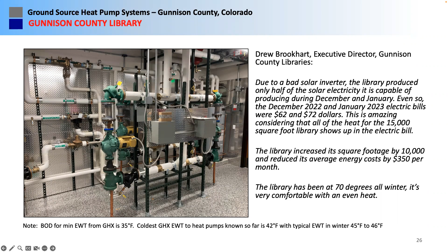The entire design team and contractors, everyone pulled together, with great communications during design and construction. And the system is working a lot better than we projected. If you'll notice on the bottom of the slide, the basis of design for the ground was a minimum of 35 degrees to the heat pumps, which the heat pumps will thrive on. I think we've got a little more water flow running through some of the formations. I've been told it's never been below 42 degrees feeding the heat pumps when the injection sides are working. So the system is working really nicely. Next slide, please.